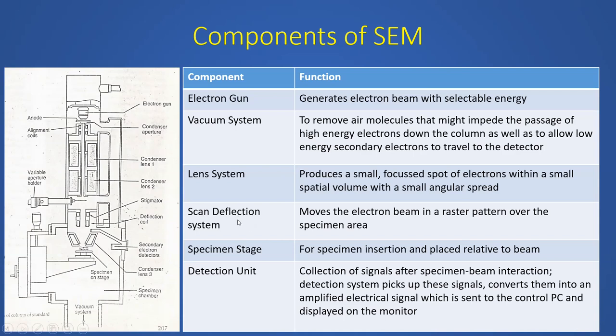Then you have a scan deflection system built into the condenser lenses. What the scan deflection system does is basically move the electron beam. If you remember, we just talked about how the electron beam has to move in a raster pattern over the specimen area. There are deflection coils here, which help the electron beam to deflect from left to right and right to left.